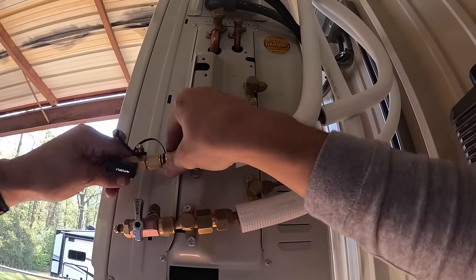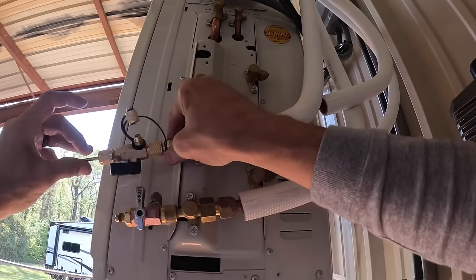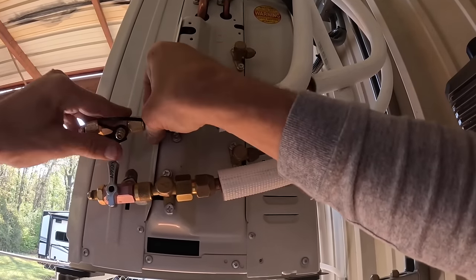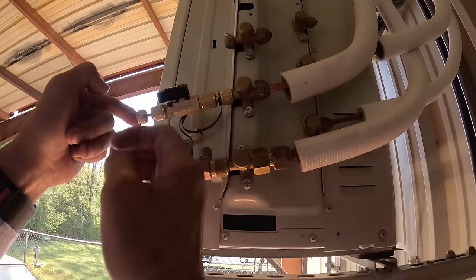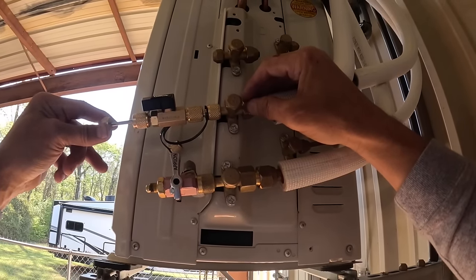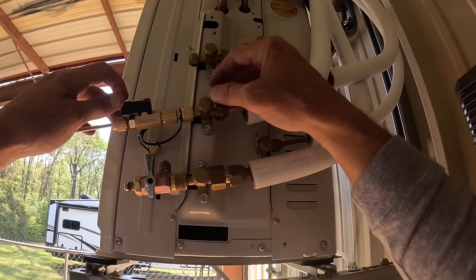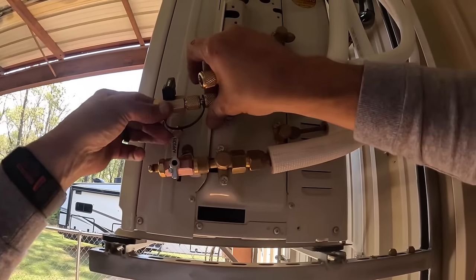All right, let's start with that one. Because we got these valves right here, I think I can pull a vacuum on the whole thing. You want the instruction sheet? No. This is either going to work or it's not. Opens up your line set into your gauges, correct? It pulls the valve core out. Yeah. And I didn't get it.